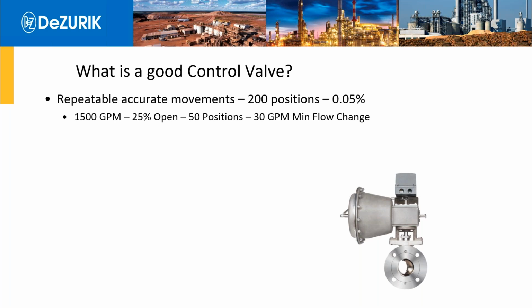So if you take a look at what that means, if you had a system with a maximum flow rate of 1,500 gallons per minute, and that valve was sized for 25% open, it was oversized, you would only be able to use 25% of those 200 positions, or have 50 usable positions of that valve. So what that means is every time that valve would move, you would get a 30 gallon per minute minimum flow change.